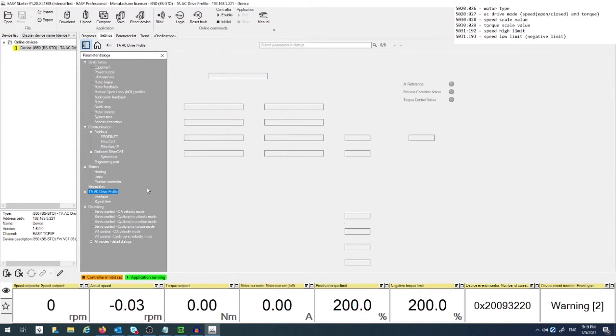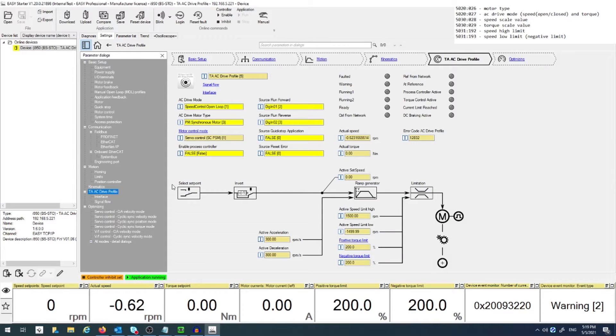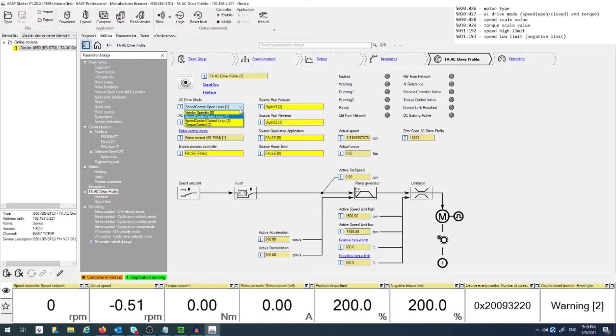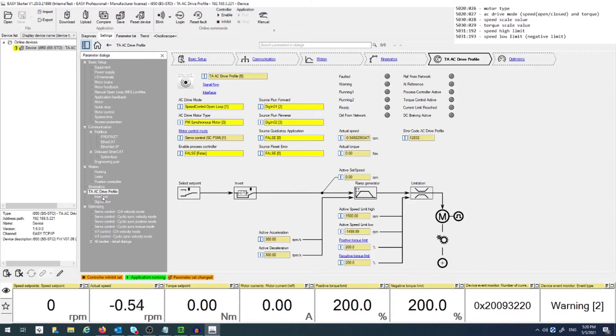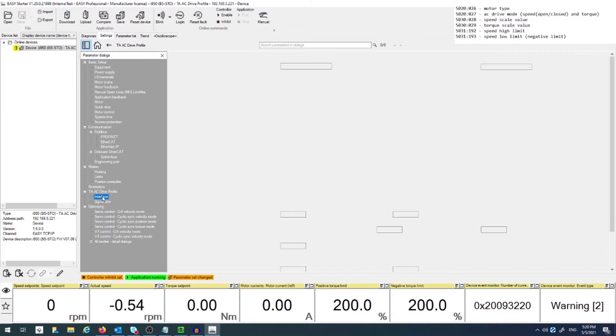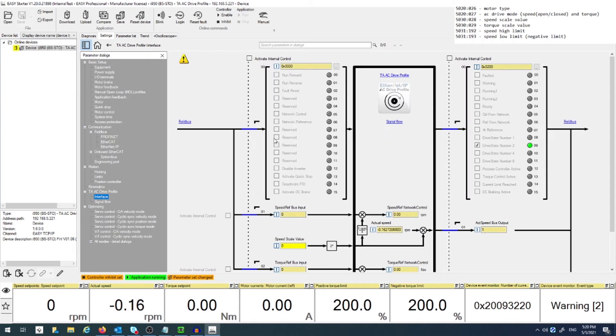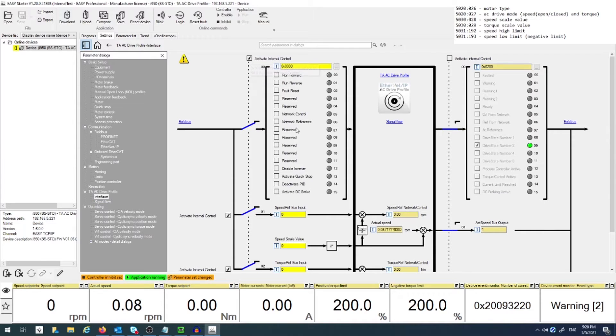Then go to the TA AC Drive Profile section. Select the AC drive mode you want — Speed or Torque Control. Afterwards, go to the Interface subsection. Here you can control the i950 through Easy Starter instead of the Field Bus by clicking on Activate Internal Control.